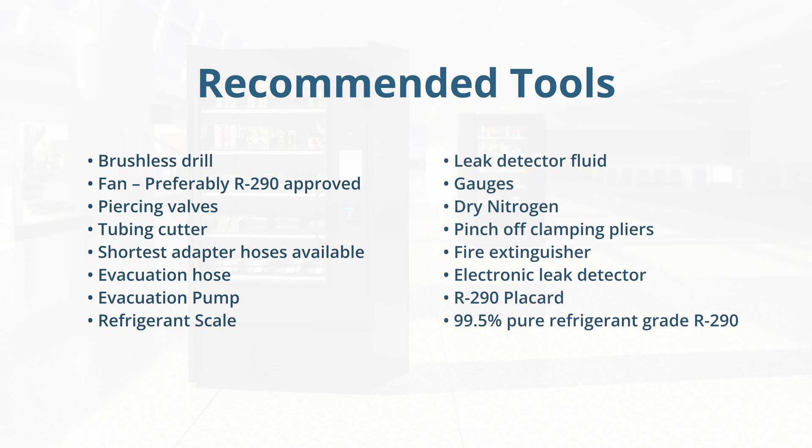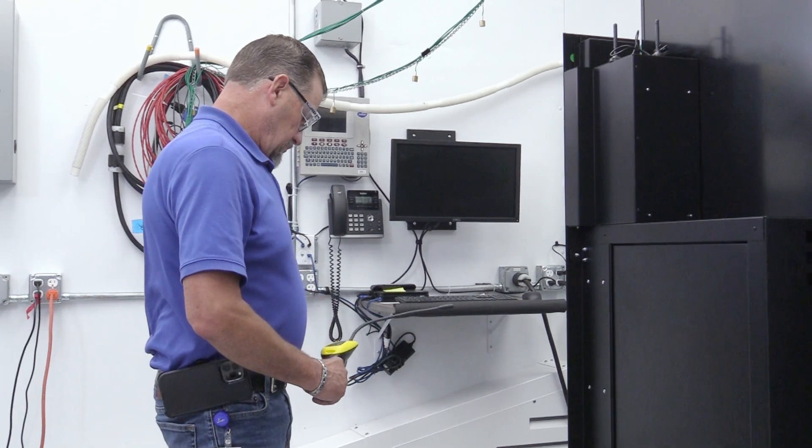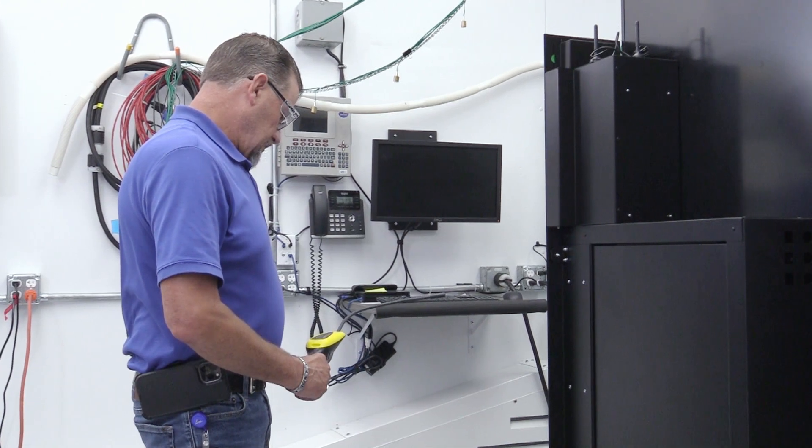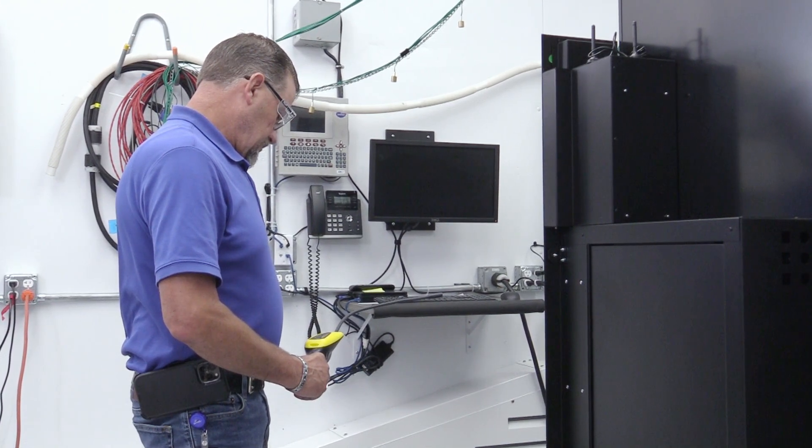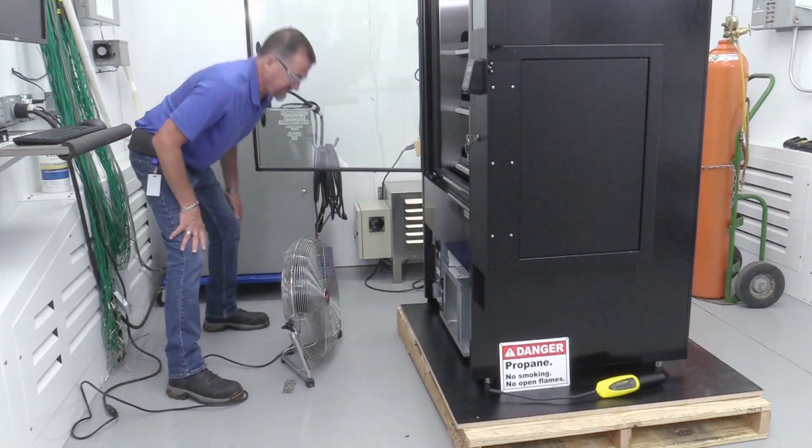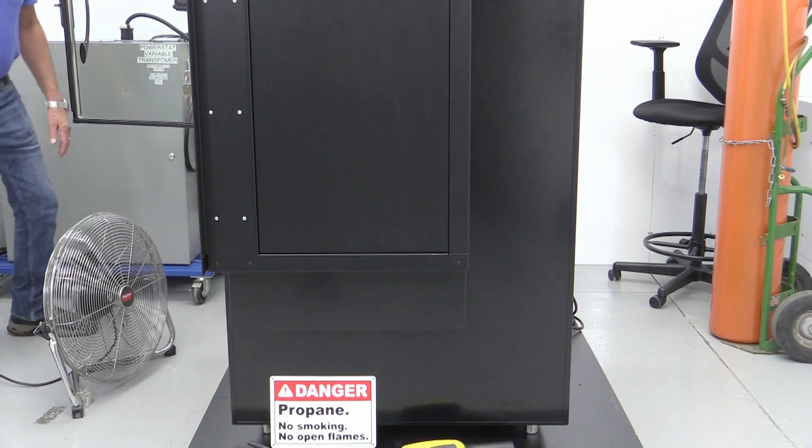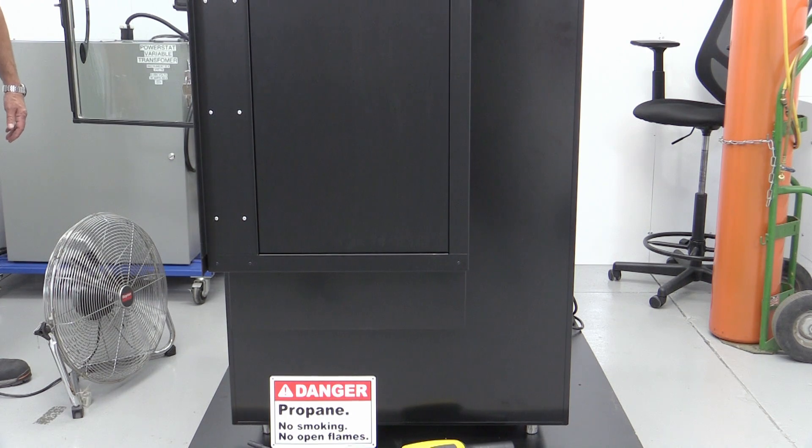To begin service of the condensing unit of an R290 unit, turn off the equipment and unplug it. Turn on the electronic leak detector and ensure that there's no combustible gas in the area before performing service. Turn on the fan and point it at the service area. We recommend an R290 approved fan. If the fan is not R290 approved, keep it 10 feet away from the service area.